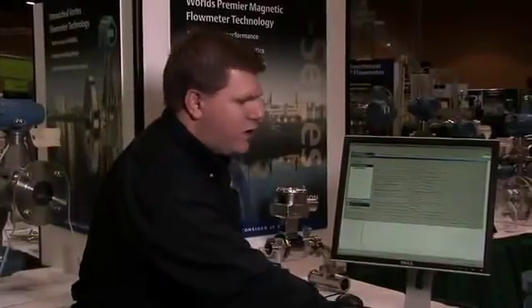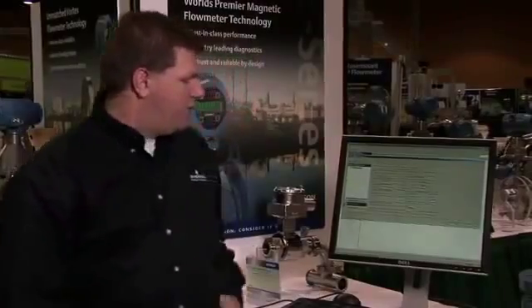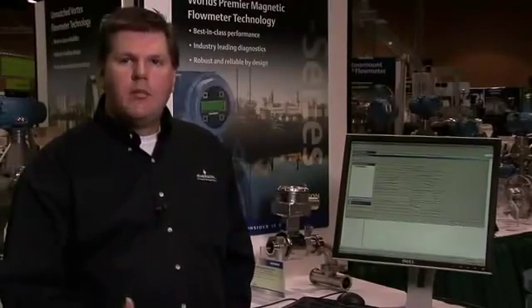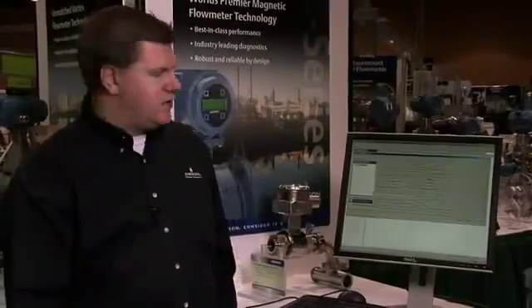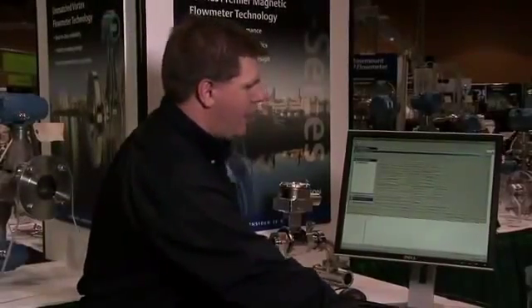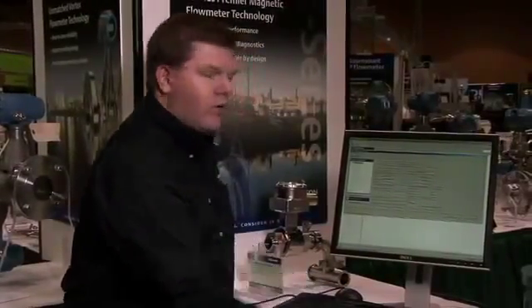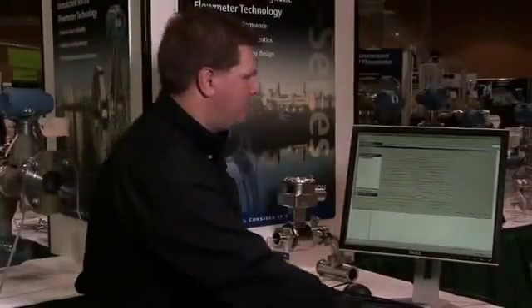The benefit of meter verification, of smart meter verification from Emerson, is that not only do you get to verify that the transmitter is functioning correctly, but it also does a complete verification of the primary element that is installed in your process piping. All of that is captured on this report, along with a block for a signature and a date, so that it is a formal report that you can submit to the auditor.